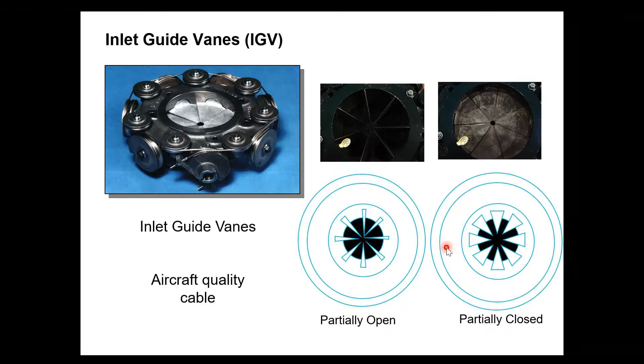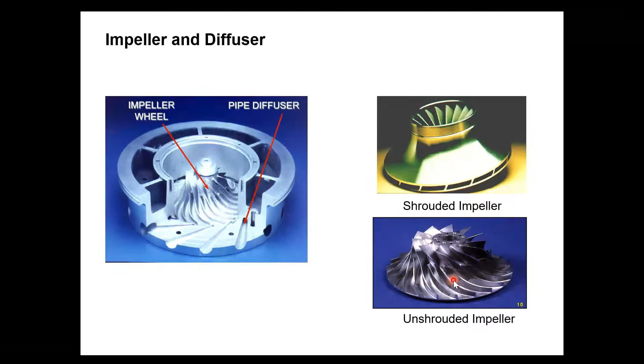This is the impeller wheel that is there, and this is the pipe diffuser shrouded impeller. Now, shroud is another important component of centrifugal chiller, which is responsible for the capacity that centrifugal chiller is delivering. It could be a shrouded impeller, it could be an unshrouded impeller. In case of a shrouded impeller, the shroud and impeller is one ensemble. In case of an unshrouded impeller, they are two different components, but they are coupled together to make the whole ensemble. So that's how these two types of impellers are different. As I said, different manufacturers have different types of impellers. There's nothing good or bad about different types of impellers, as long as it is able to deliver the capacity and the lift requirement that is required for the system.